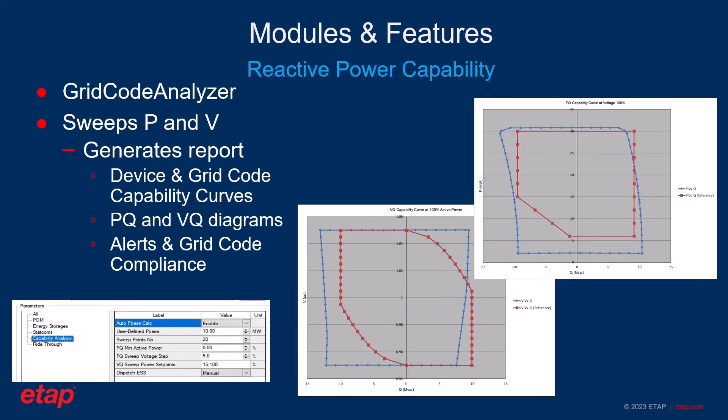In PQ studies, ETAP provides an automated sweeping structure for active power, reactive power, and voltage, and generates results based on sequential load flow calculations in the time domain. It generates a very comprehensive report including all capability information and plant calculations. The comparison between the grid code the user has chosen and the final results is presented on an overlaying basis, meaning the power plant capability and the actual grid code requirements are plotted on the same axis so the user can easily and visually determine if the grid code is met or not.